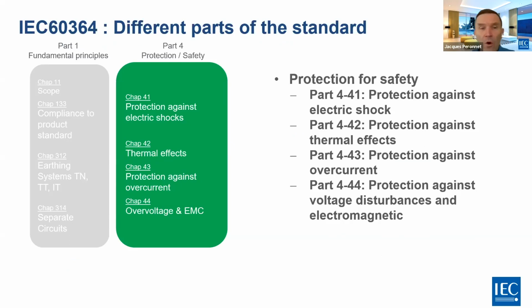Then we have what we call part 4. So part 4 is everything for the protection for safety. In part 4, we have 4 different parts applying to the different protections that we want to cover. The first part is part 441, which is for the protection against electric shock. Part 442 deals with the protection against thermal effects, so burns, fire, and so on. Part 443 is for the protection against overcurrent, so overload and short circuit. And part 444 is protection against voltage disturbance and electromagnetic disturbance.